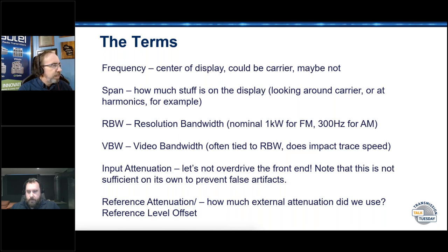Obviously, you're concerned with frequency. There's a couple ways you can set that up, depending on the analyzer. Sometimes you can set your center frequency and then do a span, like the carrier plus or minus 600K. That's an easier way to set it up. You'd go to frequency setting, hit your center on what you want to look at, then use the span setting.